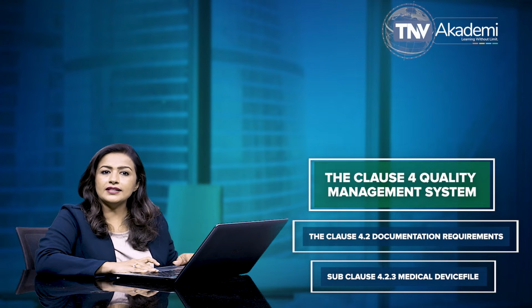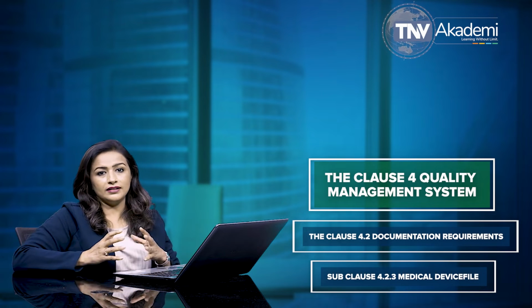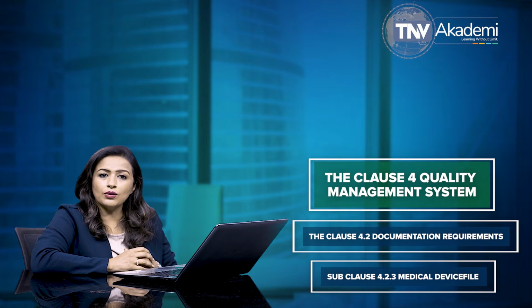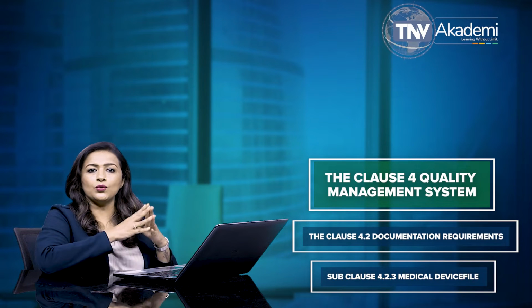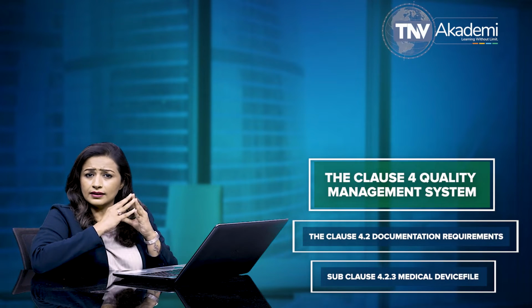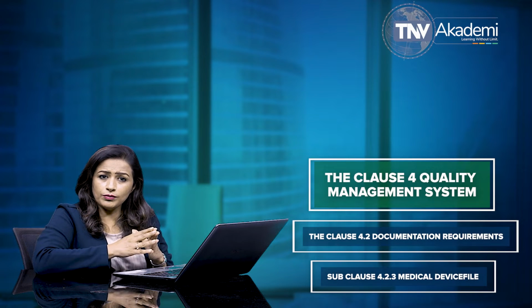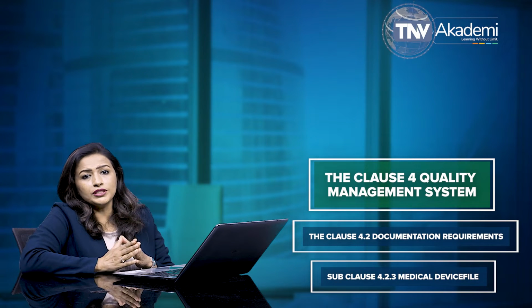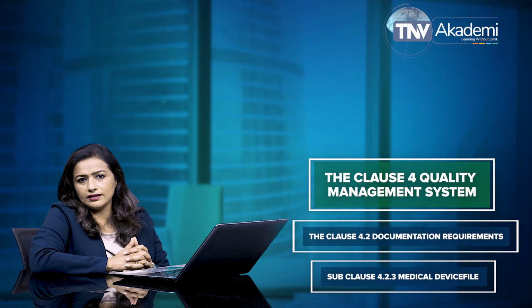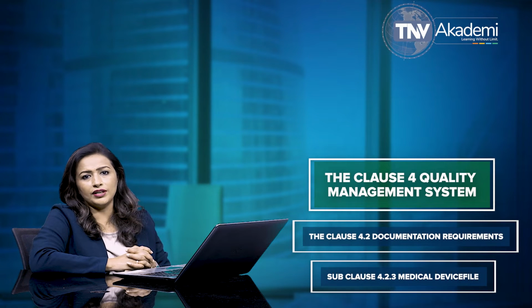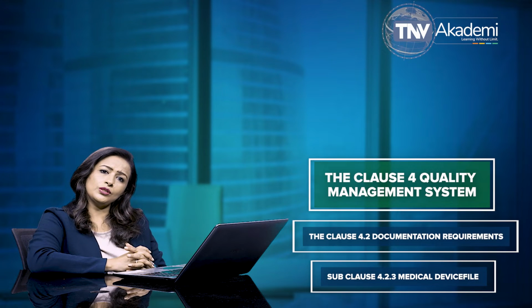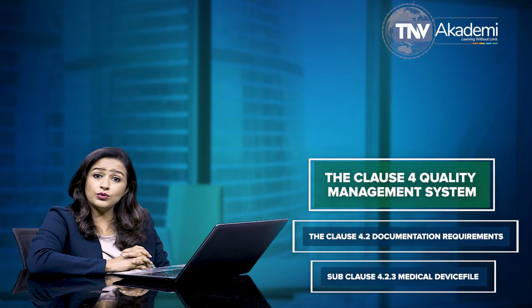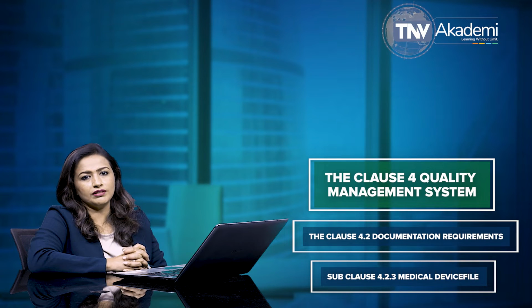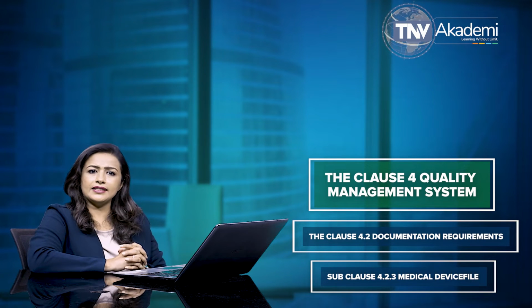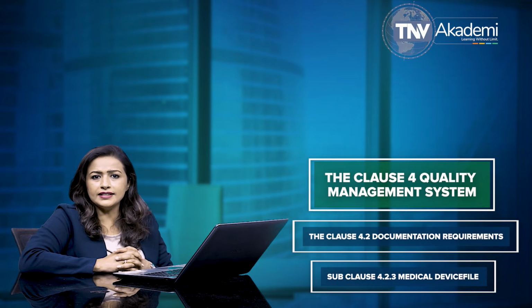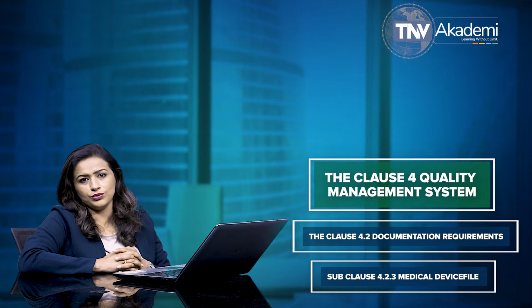This clause specifies that for each medical device type or medical device family, the organization is required to establish and maintain one or more files either containing or referencing documents generated to demonstrate conformity to the requirement of this international standard and compliance with applicable regulatory requirements. As per this clause, the content of the file is required to include, but is not limited to, general description of the medical device, intended use or purpose, and labeling, including any instructions for use.